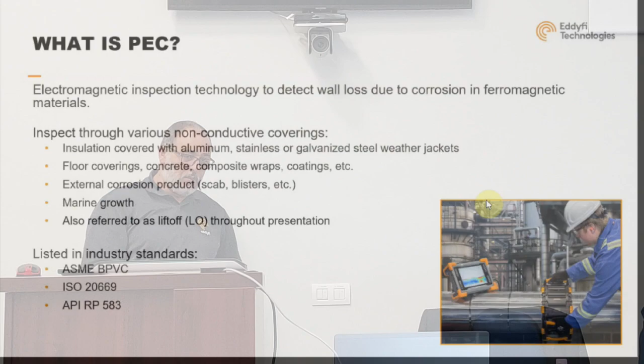So what is PEC? PEC is an electromagnetic technique, pulse eddy current, as I said, only applicable on ferromagnetic materials, so carbon steel or cast iron. No PEC possible, not with this instrument, I would say, on stainless steel piping, for example. The goal is, as I said, to inspect through different types of non-conductive insulation. And if the insulation is covered with aluminum, stainless steel, or galvanized weather jacket, up to 1.5 millimeter, you don't have to remove anything. You see an illustration on the picture at the bottom right of the slide.